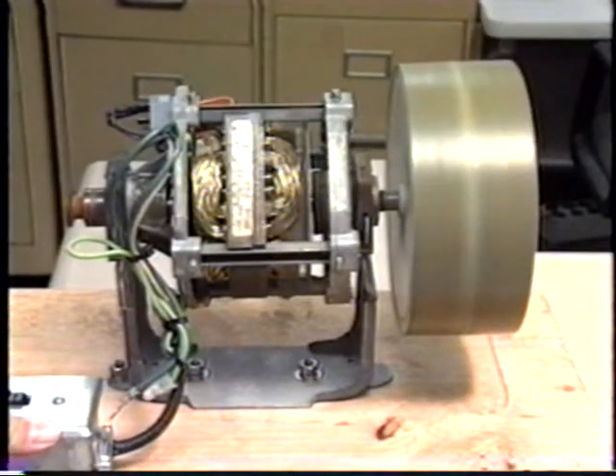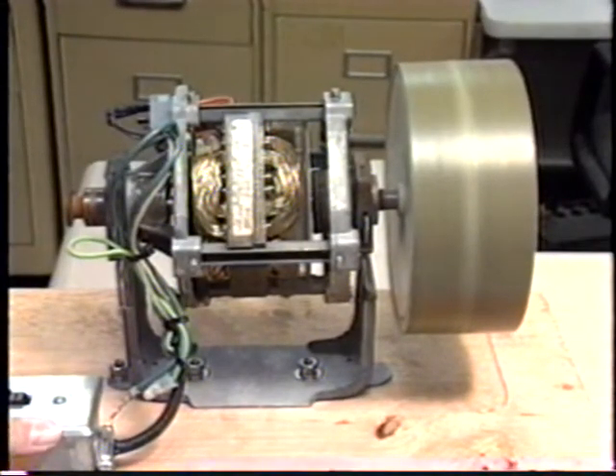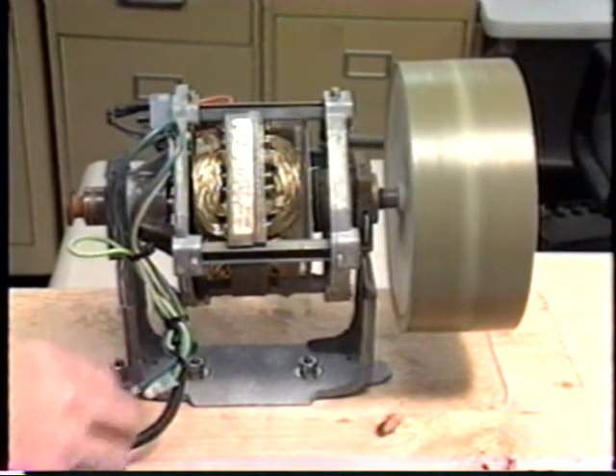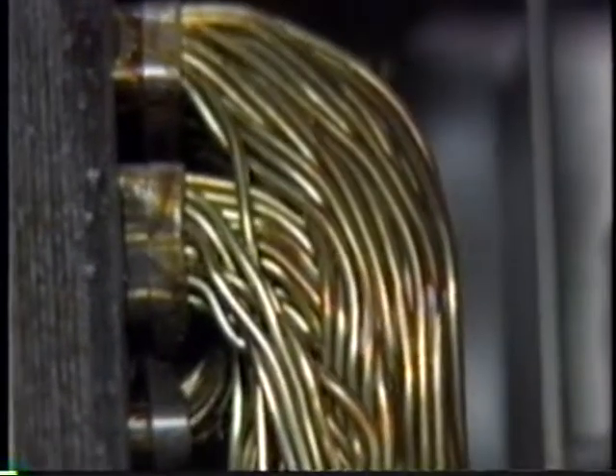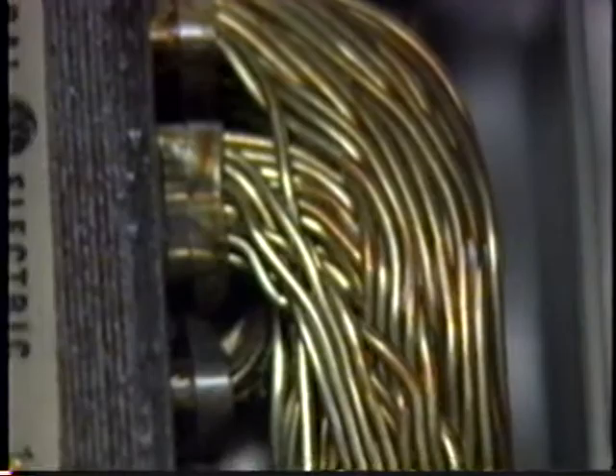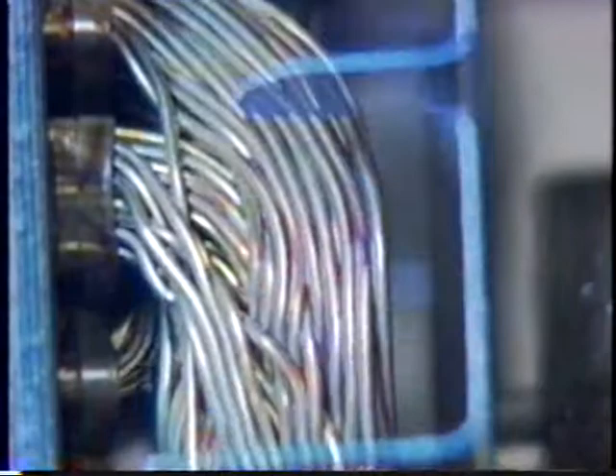The drum on the end of the motor shaft is there simply to create a load, which the motor must turn. To the naked eye, the motor works perfectly well when switched on. But when a strobe light is shined on the motor windings, the presence of a problem is unmistakable. Internal wear has led to a wobble in the shaft, which will eventually destroy the motor and may destroy a coupling or even the driven unit in the process.